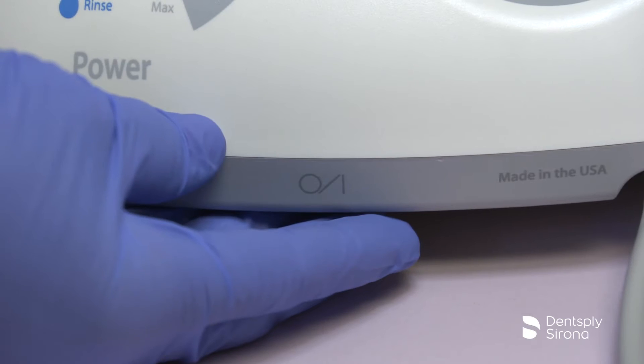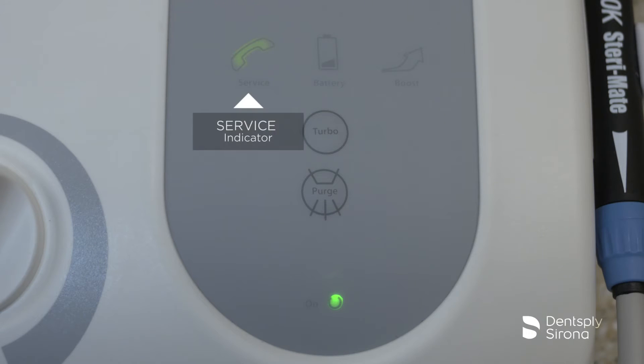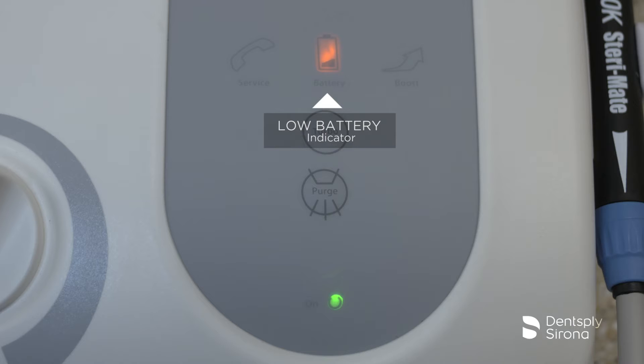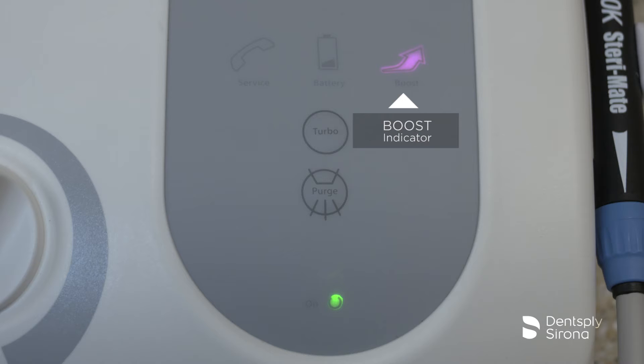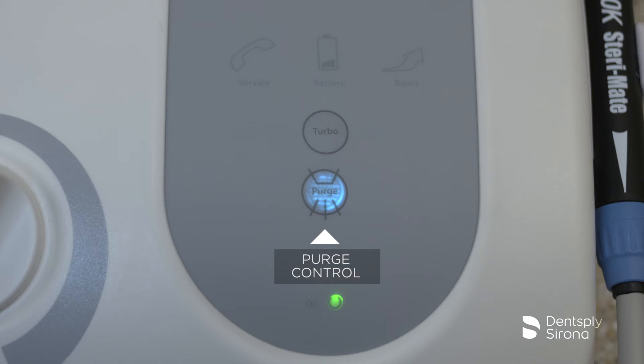The power indicator button illuminates when the main power control switch is on. The service indicator will illuminate when the system is not functioning properly. The low battery button illuminates when the tap-on foot pedal battery is approaching end of life. The boost indicator illuminates when boost mode has been activated with the tap-on foot pedal. The turbo mode indicator illuminates when turbo mode is on; when on, up to 25% extra power is delivered, increasing the stroke of the tip. Turbo power remains on until the button is pressed again or the unit is turned off. The purge control button illuminates when the purge function is activated.